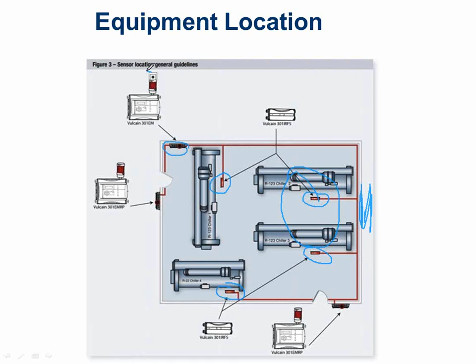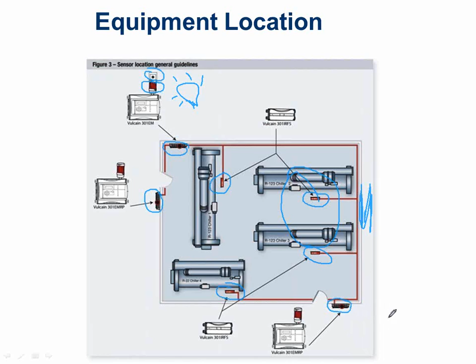Inside the room, I have an annunciation panel. In this particular case, there's both a horn and a strobe light built into that panel. It's fine if you have them separate. You can have the panel turning on a relay, and the relay can be turning on the little light bulb. Look how good of an artist I am, right? Turning on my light bulb and sounding my horn separately, that's fine. But I have to have the strobe light and I have to have the horn. Additionally, outside every door to the room, whether it goes into another mechanical room, to a hallway, or to the exterior outdoors, I have to have some way to have a strobe light and a horn out there. I don't necessarily have to have a panel, but I have to have a strobe light and a horn at the very minimum. That way no one goes into the room unexpectedly. All right, so that's my ASHRAE standard, if you will.